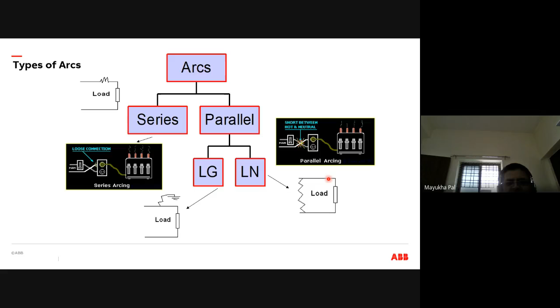So in that context, parallel arc can again be of two types, and it is due to the short circuit between those. So that's going to be huge. Detecting these appropriately, we have many devices, so it's nothing new. One of such devices that we use in homes, in your load centers, are AFCI, arc fault circuit interrupters, or arc fault detection devices. AFCI is a UL type of device, AFDD is an IEC type of device. And then you also have ARCvault for bigger industrial applications. So all these devices are well available.